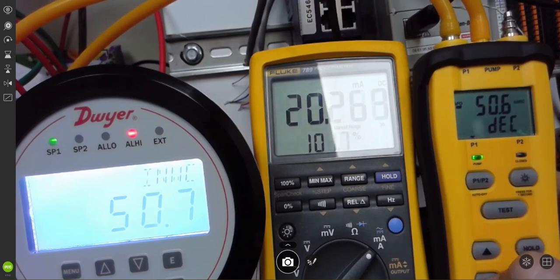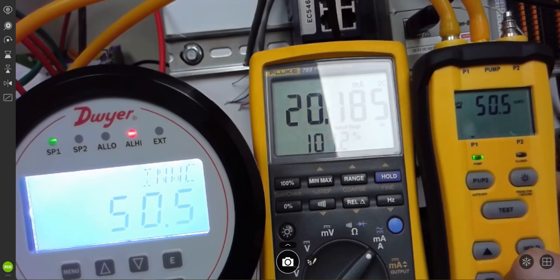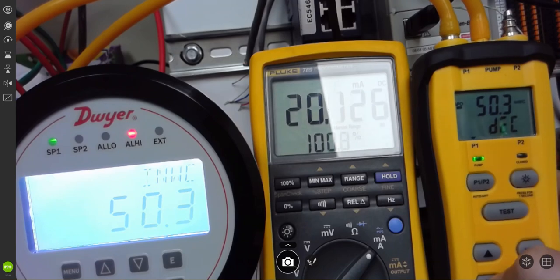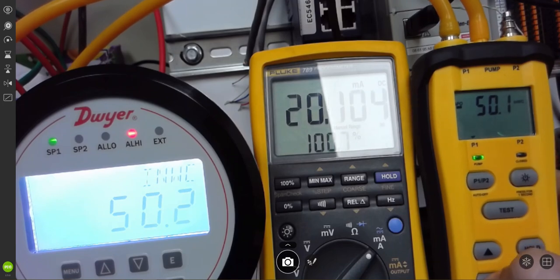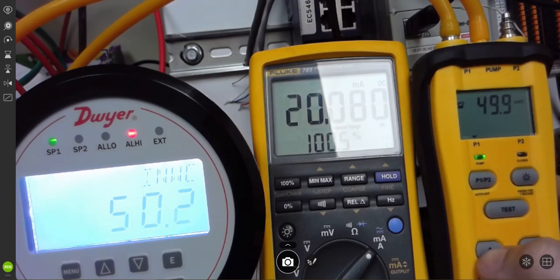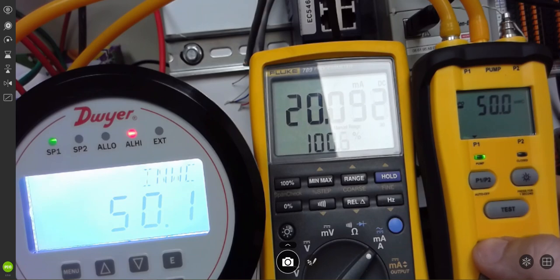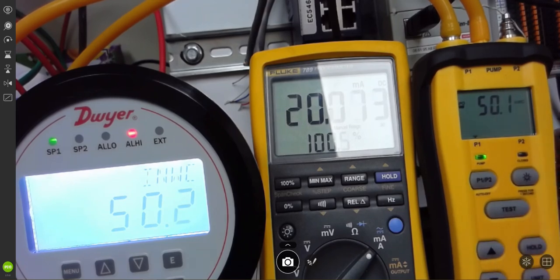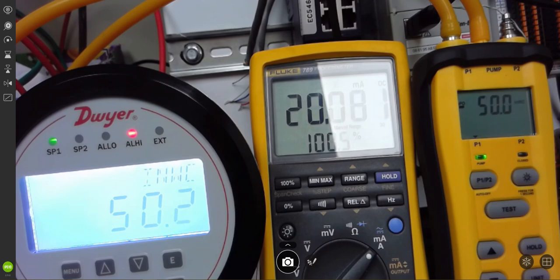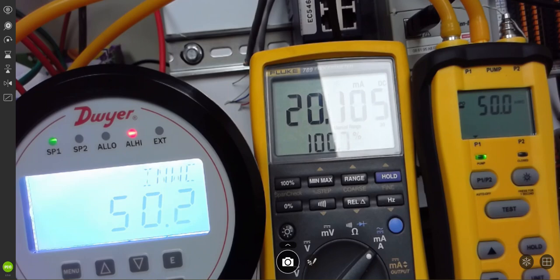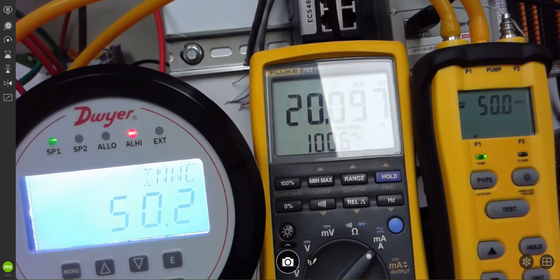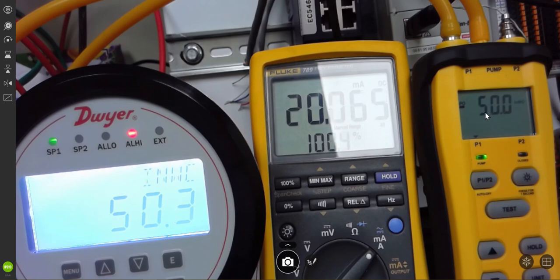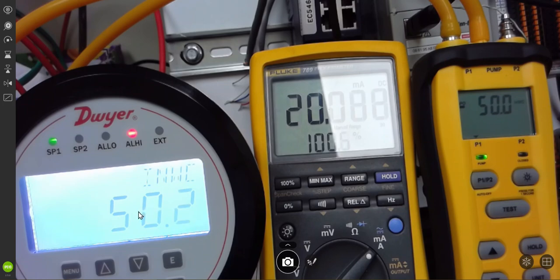We're going to keep going down a little bit. Getting close. And we may not get precise, but let's see where we settled out. Well, that's pretty close right there. That's kind of hovering. So in this instance here, if we were to look here, you would see that I am actually simulating 50 inches of water column. My meter is reading anywhere between 50.1 and 50.2, which is well within the tolerance of this sensor.